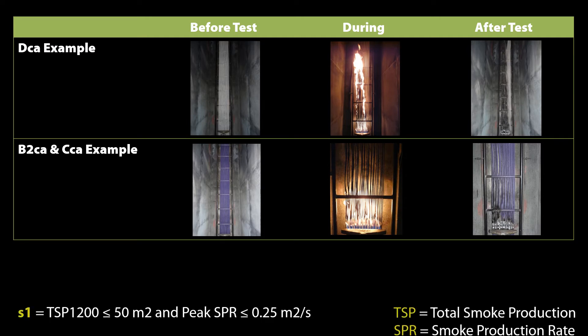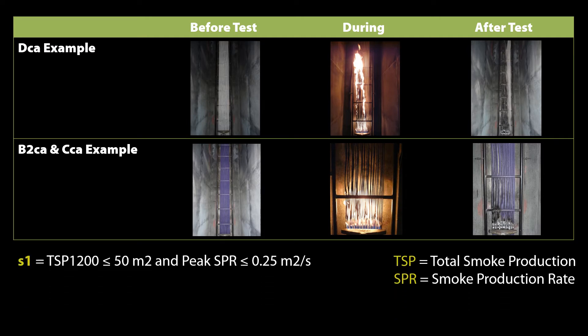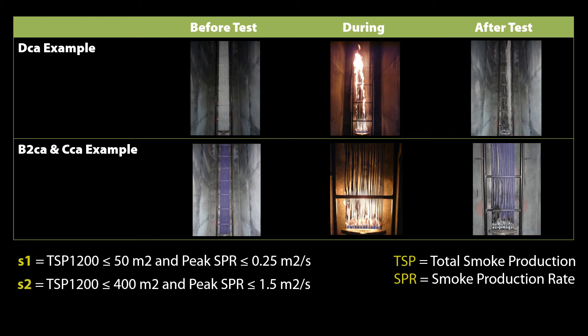The smoke production classification has three levels. S1 has the following limits: total smoke production of 50 square meters with a peak smoke production rate of less than 0.25 square meters per second. S2 is less than 400 square meters at a rate of no more than 1.5 square meters per second. Lastly, S3 is very simple — it does not meet either S1 or S2.